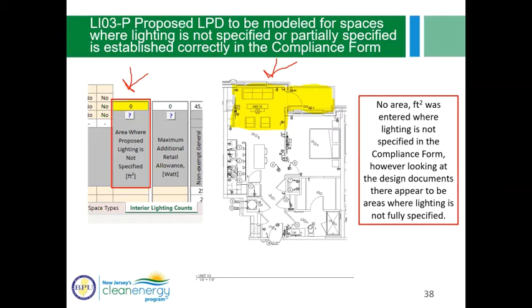Here's a screenshot of the actual design documents. We can clearly see this area in yellow, the living room, and the objects shown are just receptacles. There are no lighting fixtures specified here. So we'd expect this to be a non-zero number. This needs to be addressed in the submittal, because an area where proposed lighting is not specified was not entered correctly, or at all, in the compliance form. That needs to be corrected.